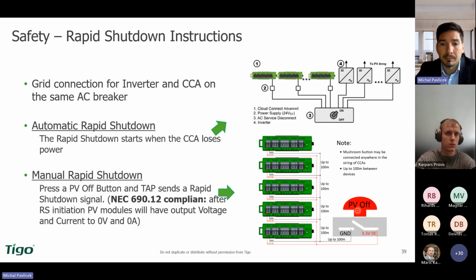If you touch this button and you connect the relay in this CCA unit, it automatically brings optimizers and rapid shutdown control in the safe mode. That means that each box will reduce the voltage to 0.6 volt. The 0.6 volt is a control voltage. So if you have 10 optimizers and you check the voltage in the string when it's closed, there should be 6 volt in such case, 10 by 0.6. So we can control everything is working well and there's no issue.